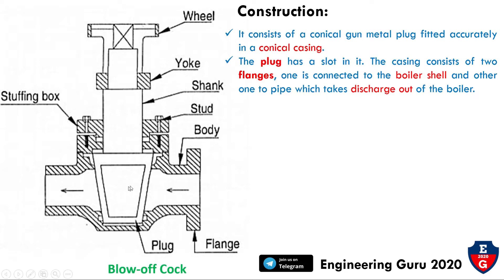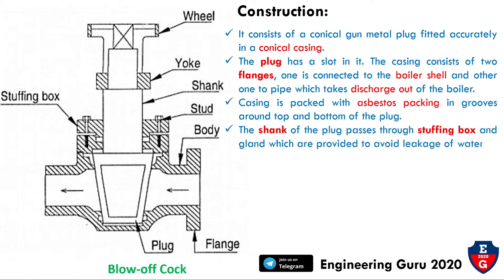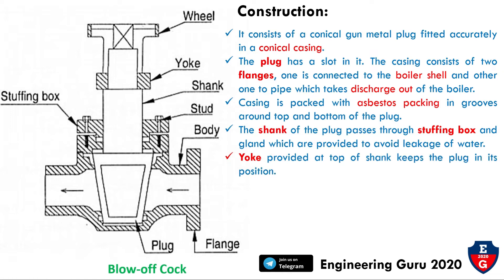The casing is packed with asbestos packing in grooves around the top and bottom of the plug, as seen in the figure. The shank of the plug passes through the stuffing box and gland, which are provided to avoid leakage of water. The yoke is provided at the top of the shank and keeps the plug in its position.